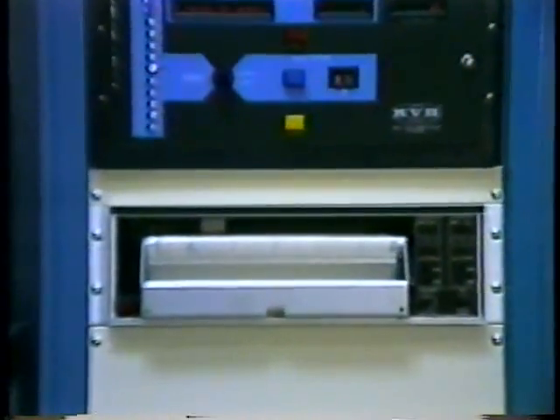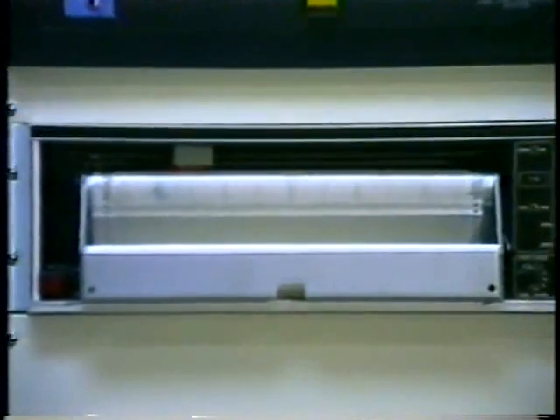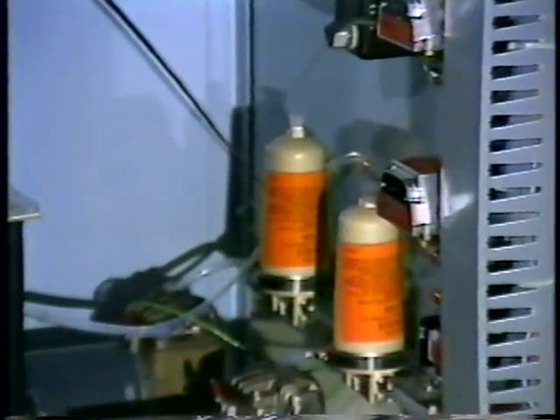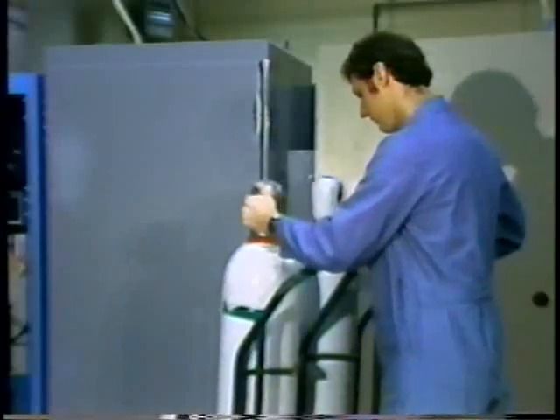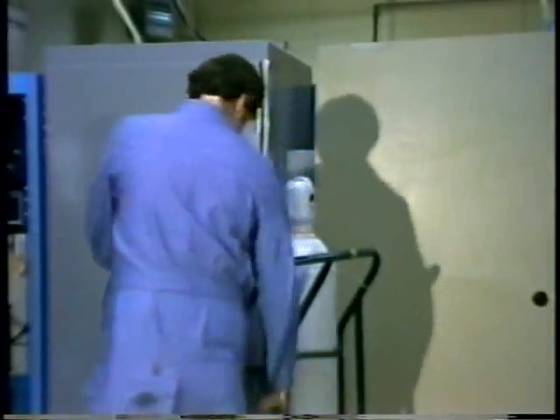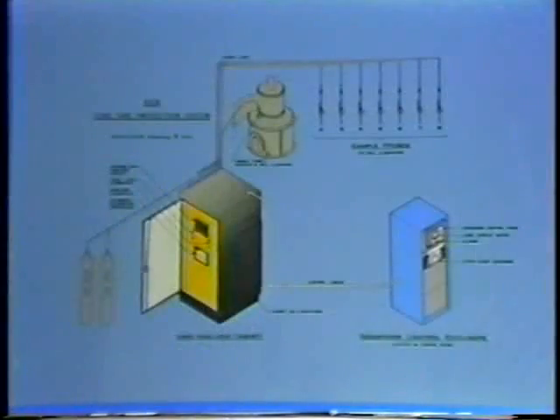Permanent records of the carbon monoxide levels of each hazardous location may be recorded on the strip chart recorder. The computer-controlled system provides low-cost installation and minimum maintenance. The computer has self-diagnostic capabilities for every component and every function. Regular service requires that the line filter elements be checked and changed if necessary. Every 6 to 8 months it is expected that the calibration gas will require replenishment.